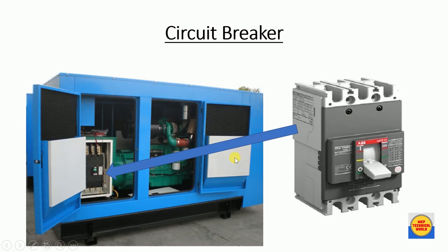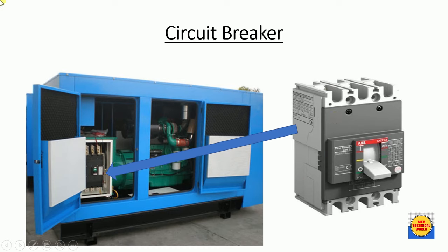Finally, the circuit breaker — specifically an MCCB — is fitted at the output terminal of the DG. The output cable from the MCCB is connected to a synchronization panel or ATS panel and then to the load. This circuit breaker protects the alternator from overload and short circuit conditions. These are all the major parts of a diesel generator.